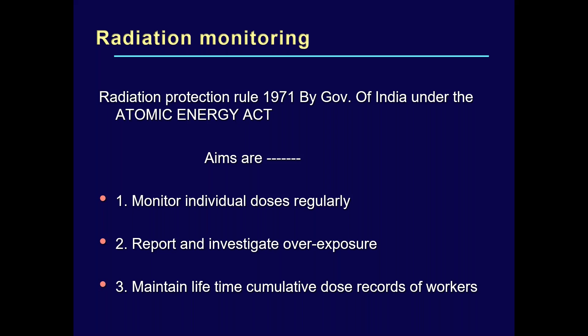So there are various types of personal dosimeters like a film badge, thermoluminescent dosimeters, and these thermoluminescent dosimeters we can assess only after 3 months, because a radiation accident we cannot know immediately. So for that purpose we have pocket dosimeters and bleepers, which will give bleeps depending upon the intensity of radiation. These kinds of radiation instruments are used by the radiologist, nuclear medicine specialist, technologist, and the radiation safety officer to handle radiation emergencies. And these personal monitoring TLD badges are worn by every radiation worker. And if you are posted in a radiation work area doing C-arm intervention, you should demand a film badge, and you should wear it routinely whenever you are in the radiation area.